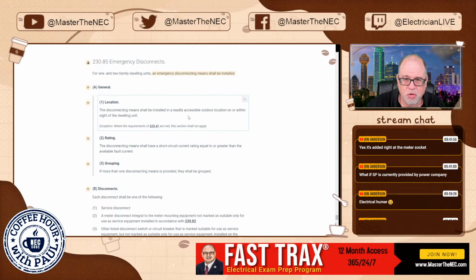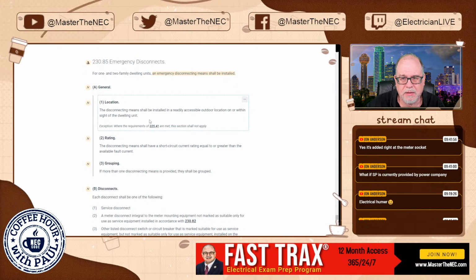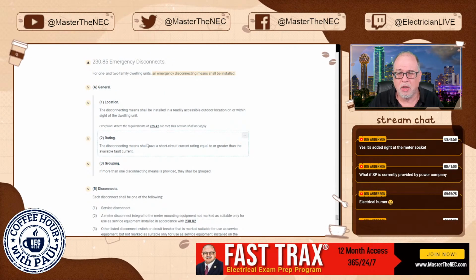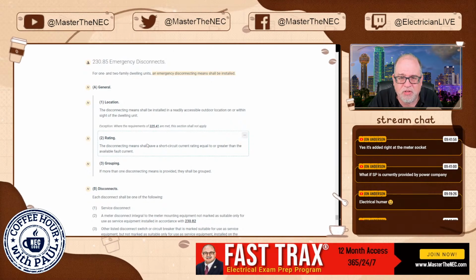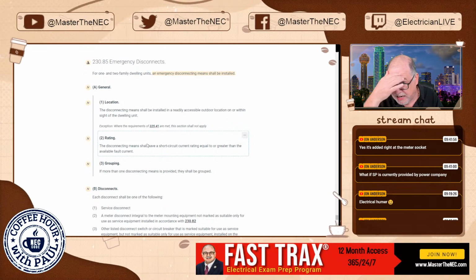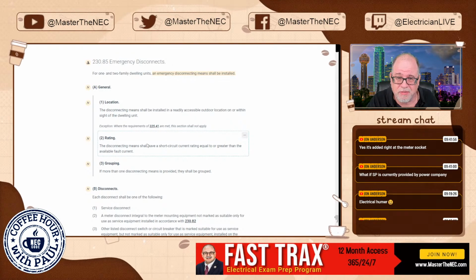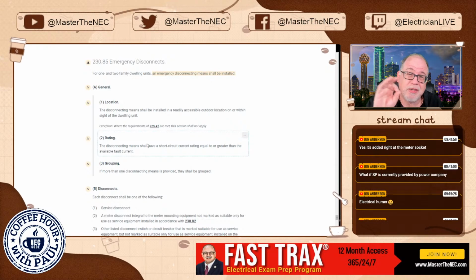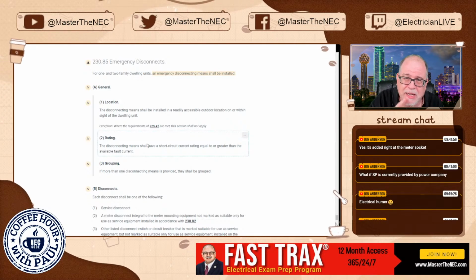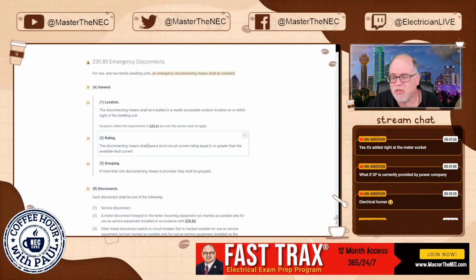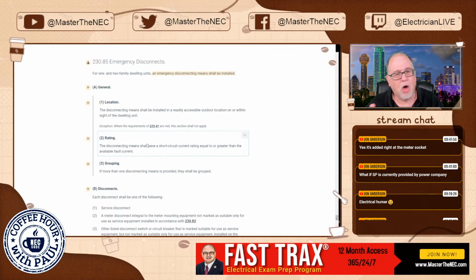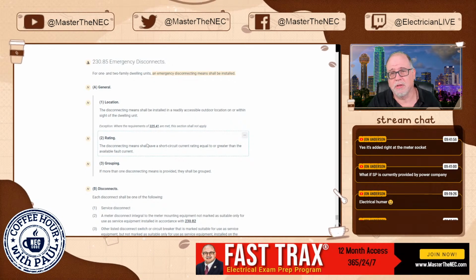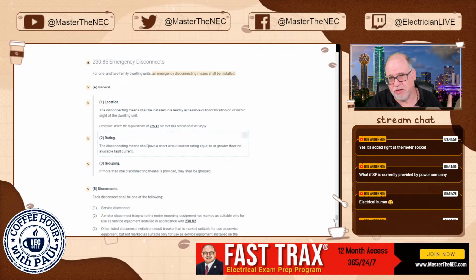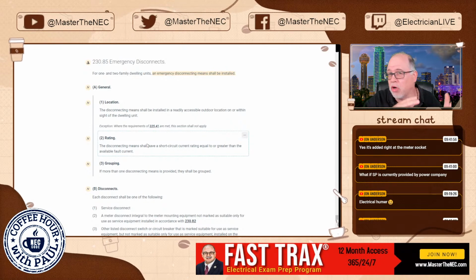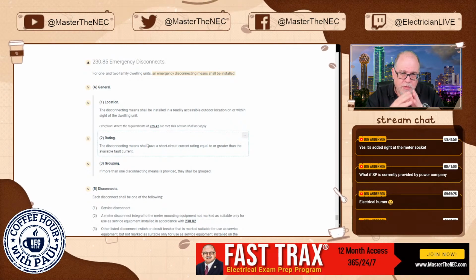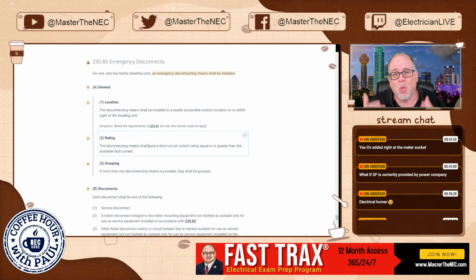All right, it's an outside location or within sight of the dwelling unit, okay? So it can be on it or within sight. And we all know what the definition of within sight is, okay? Direct line of sight and not more than 50 feet, okay? And we have definitions of that in Article 100. Oh, the other interesting thing about the 2023 edition of the National Electrical Code, I'm going to be covering this in a separate live stream, is that all of the definitions have been moved over to where? Article 100. Every definition. There's no longer .2 definitions anymore. They're all going to be in Article 100. So what did that do to Article 100? That exploded Article 100. But at least they're all in one place, right?